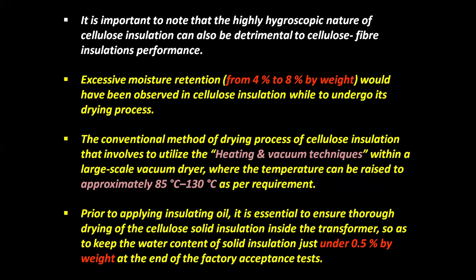Prior to applying insulating oil, it is essential to ensure thorough drying of the cellulose solid insulation inside the transformer, so as to keep the water content of solid insulation just under 0.5% by weight at the end of the factory acceptance tests.